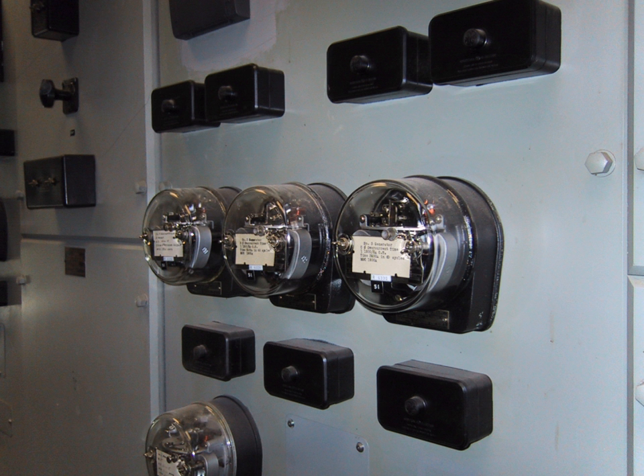Several operating coils can be used to provide bias to the relay, allowing the sensitivity of response in one circuit to be controlled by another. Various combinations of operate torque and restraint torque can be produced in the relay. By use of a permanent magnet in the magnetic circuit, a relay can be made to respond to current in one direction differently from in another.